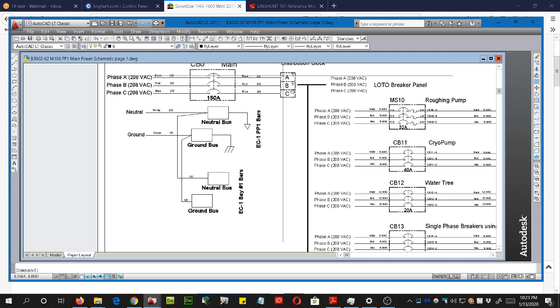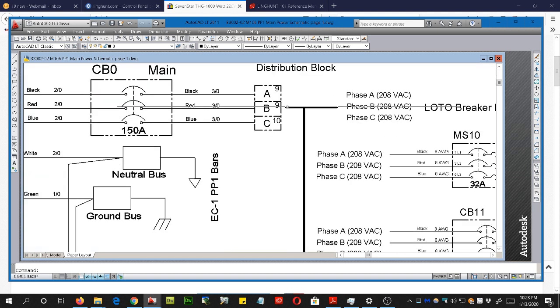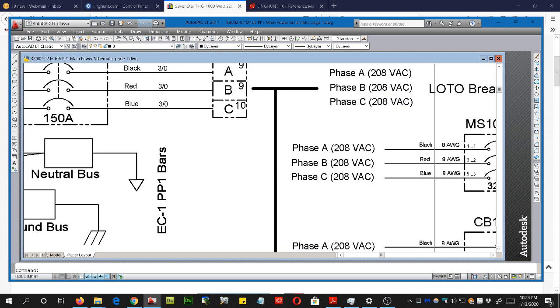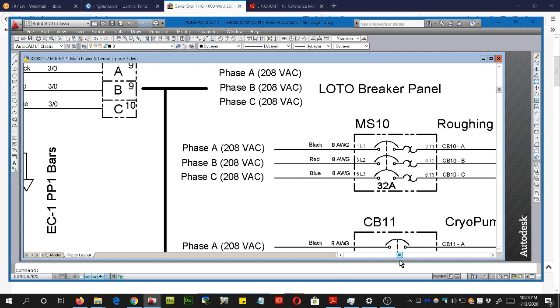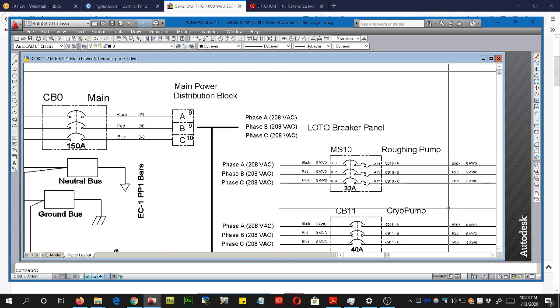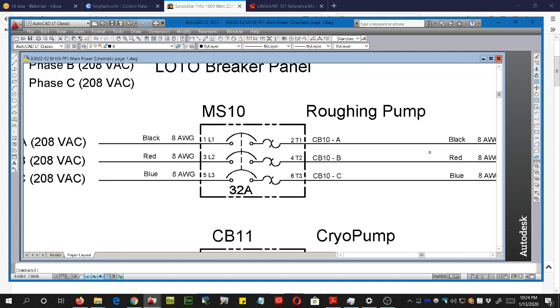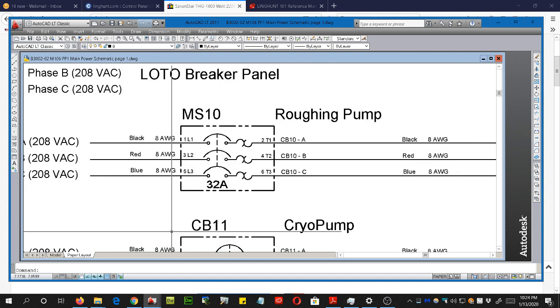So anyway, here I dropped to a disconnect, a distribution block. So I got 3 of them for each phase: phase 1, phase 2, phase 3. The colors, you guys like colors. Black, red, blue for 208 and 240. And it's brown, orange, yellow if I'm at 480 or 400 volt. Yeah, 400 volt. Yep, that's part of the requirements for sending stuff to different parts of the world.